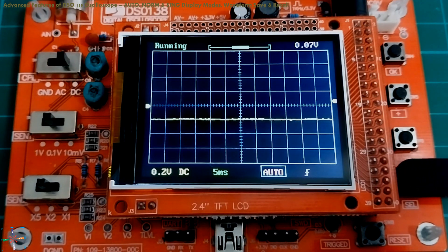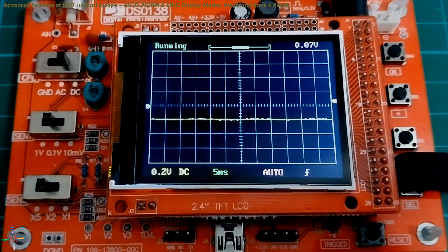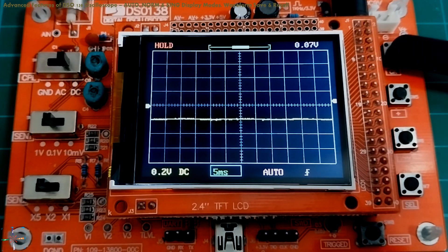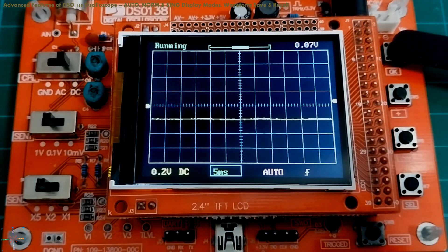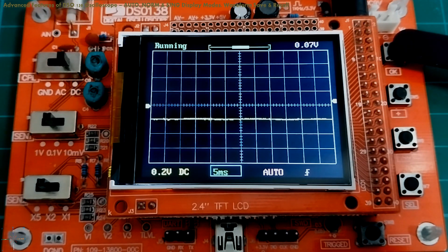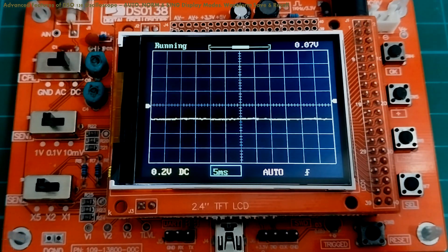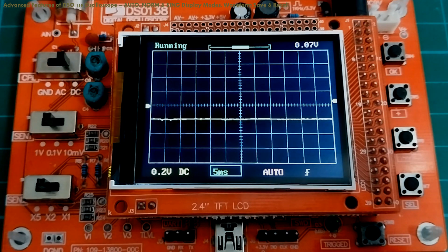Now, again using the select push button, set focus on the time division icon and make sure that your screen display is not paused. The display at the top left corner of the screen should read 'running,' not 'hold.' If you have paused the display, set focus on the time division icon and then push the OK button — that will resume signal display in auto mode.